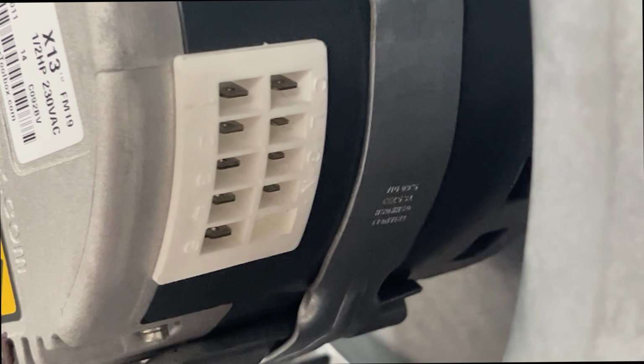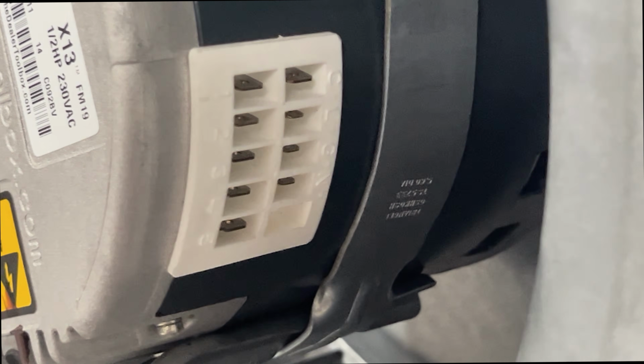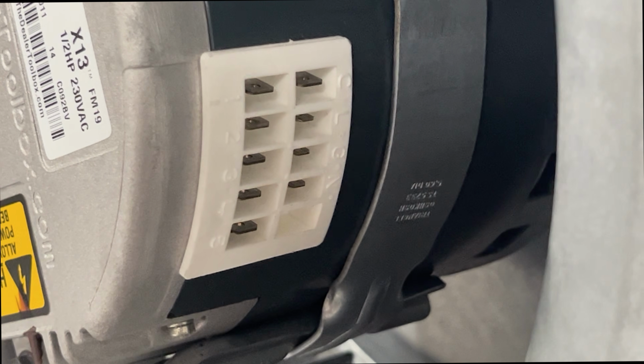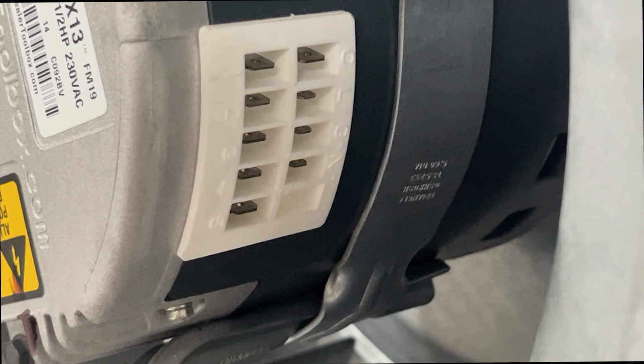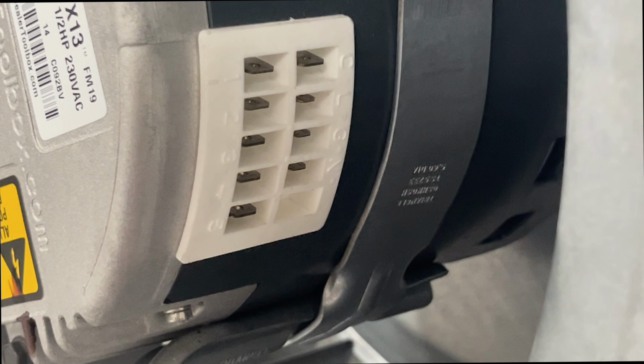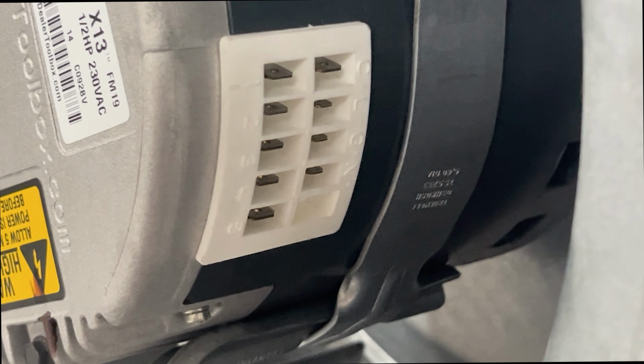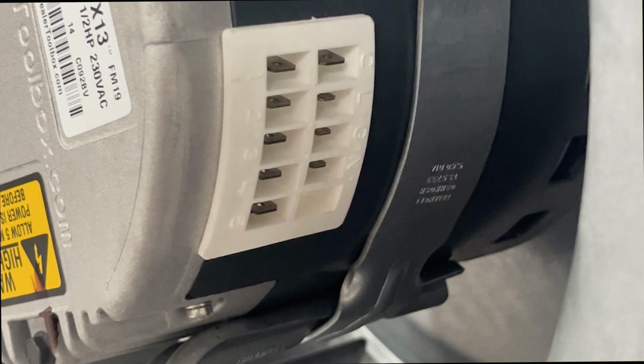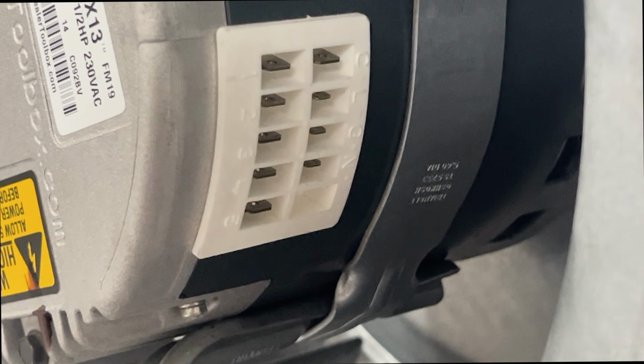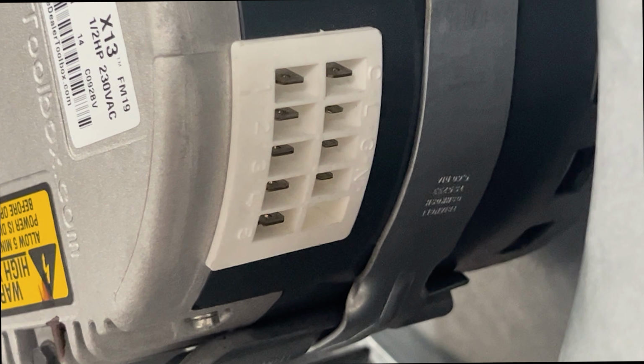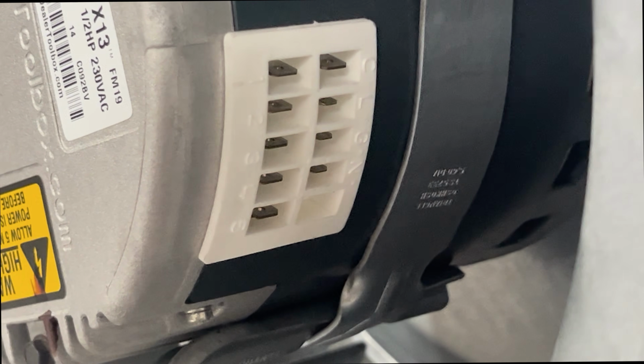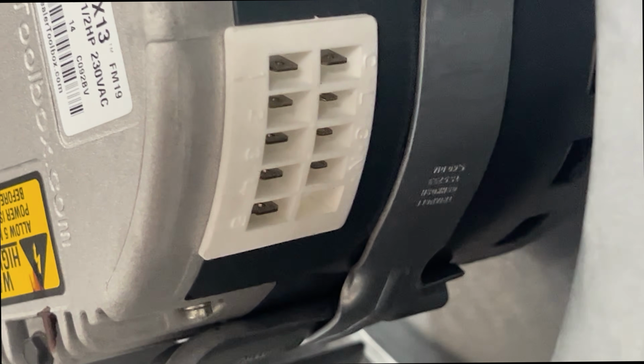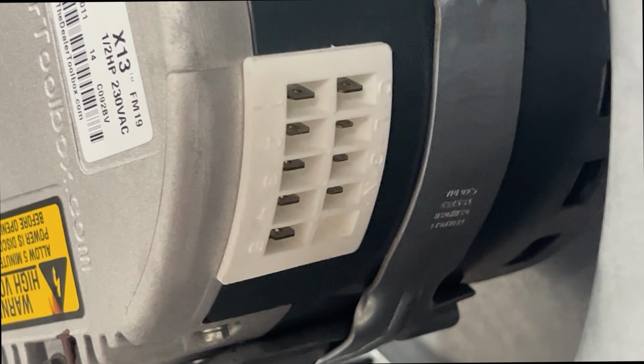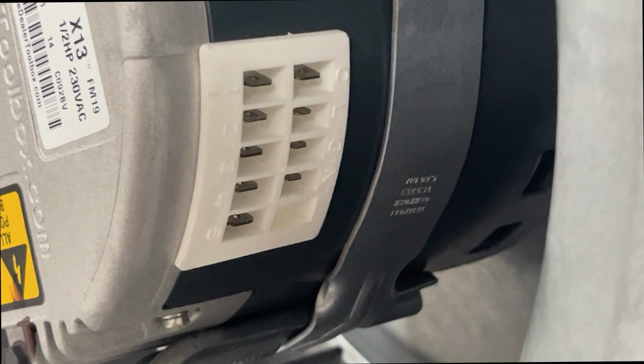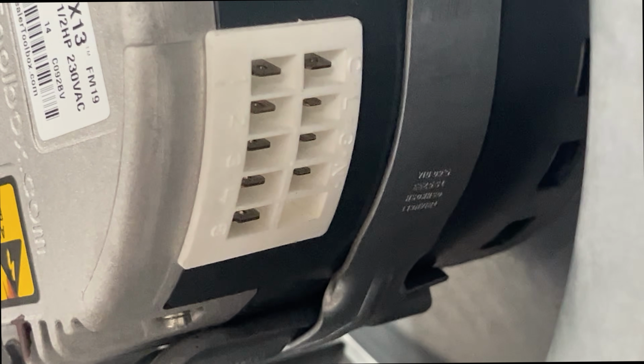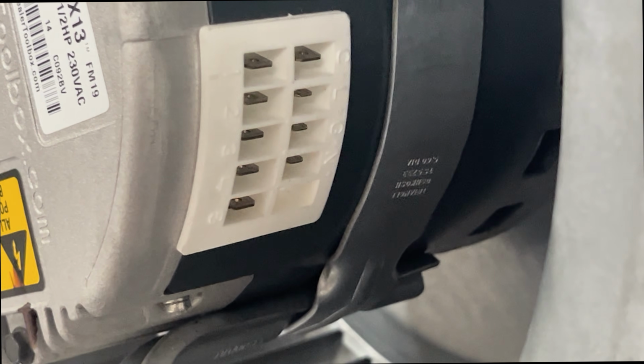So I'm going to give you this perspective, and we're going to wire these up with alligator clips. And with those alligator clips, we can move these speeds around. And also I want to show you that if I used the L for one line and the N, instead of wiring it to the second line, I can wire that N to neutral, okay? And I will be able to take this 230 volt motor and run it on 120 volts. Now the amp draw will double. We're getting about 1.1 amps with it outside of the cabinet. And there's not much resistance on it, so it will increase the moment we put some static on it.